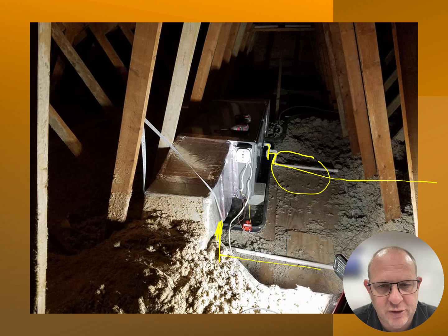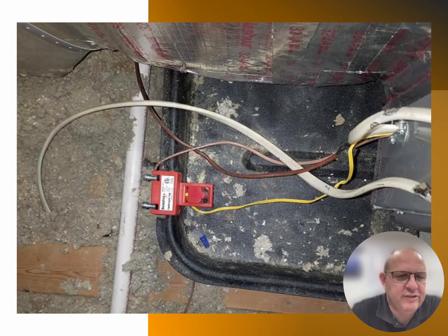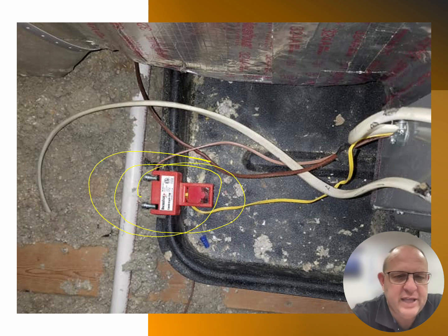On the next slide, we're going to take a closer look at that overflow switch that's on that drain pan. As water is coming up into the drain pan, this switch, if it gets too full, will shut off the air conditioner so that it will not run anymore and will not be dumping any more condensation into the pan. This is also going to alert the customer that there is an issue with the air conditioner when they don't have any cooling inside of their apartment or their house.